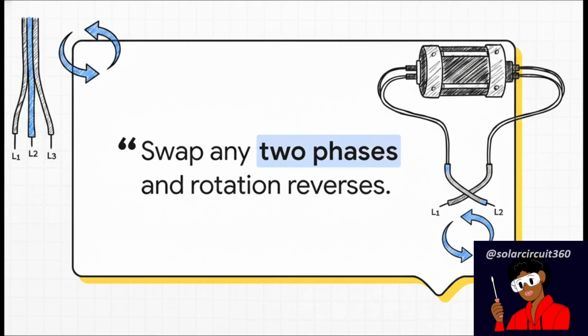So here is the golden rule of three-phase systems. If you remember absolutely nothing else from this explainer, remember this undeniable fact. Swap any two phases and rotation reverses. That's the whole shebang. If you discover through your phase rotation meter or your jog test that the motor is running backward, the fix is simple. All you have to do is safely de-energize the system, perform your lockout/tagout, and swap any two of your three-phase conductors. For example, just switch L1 with L2.